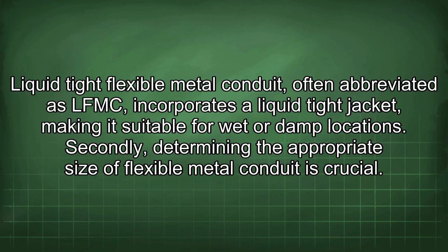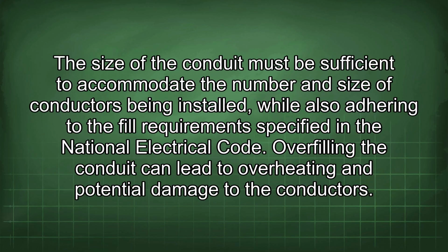Secondly, determining the appropriate size of flexible metal conduit is crucial. The size of the conduit must be sufficient to accommodate the number and size of conductors being installed, while also adhering to the fill requirements specified in the National Electrical Code. Overfilling the conduit can lead to overheating and potential damage to the conductors.